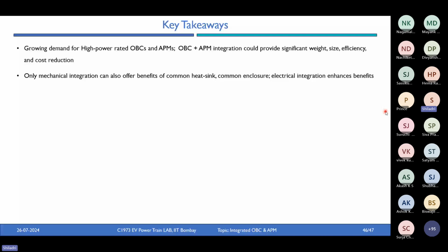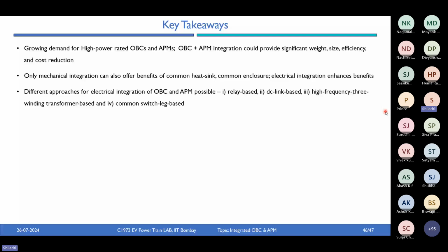There are broadly four ways of doing electrical integration: relay-based, DC-link based, three-winding transformer-based, and common switch leg-based. Each has some good points and bad points, which I talked about. The three-winding transformer in particular has control coupling challenges, which can be addressed through things like a decoupling matrix and designing the transformer properly, but these challenges still exist.